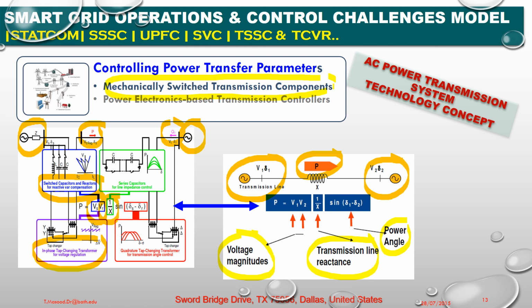For the third parameter, the sending and receiving end load angle is controlled by quadrature tap changers or transformers for transmission angle control. So these four devices are used to control voltage magnitude, transmission line reactance, and power angle, to deliver maximum power and maintain seamless operation.